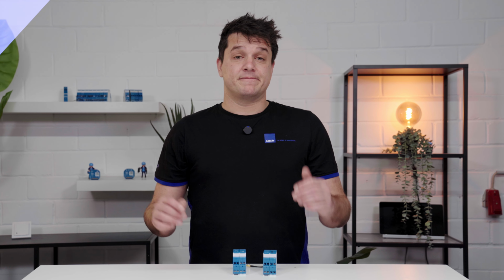You can operate up to 64 DALI and DALI-2 control devices, as well as 64 DALI-2 sensors on the FD2G14. The gateway controls DALI devices with EnOcean sensor telegrams. You have the option to control 16 groups or send a broadcast command. With the DALI cockpit software, you can configure DALI components. We program a broadcast command as a universal button in our example.